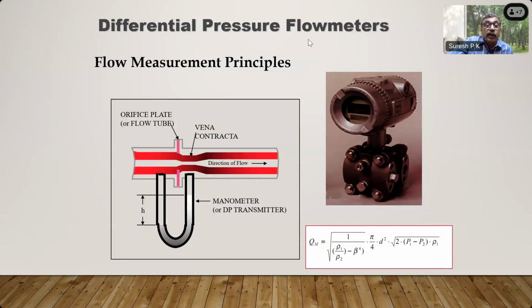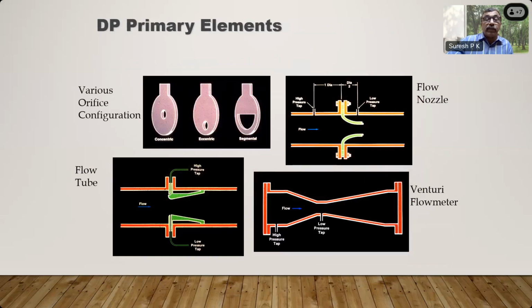I hope you can see this. This is the flow measuring principle of the differential pressure meter. So you have an orifice, and there is a vena contracta also. At the vena contracta, you measure the pressure. So the pressure upstream is measured, then the differential pressure gives you an indication. Not necessarily a concentric orifice; an eccentric orifice is there, a segmental orifice is there, different kinds of orifices are there. Then you have venturis, you have nozzles. These are different kinds of DP measurement, that is, differential pressure measuring instruments.